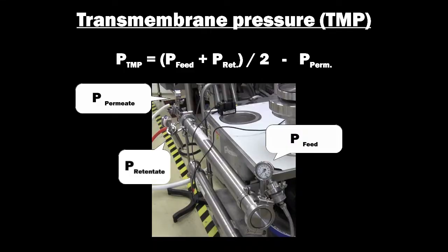The TMP can be manipulated in a couple of ways. One, adjusting the pump speed and associated feed pressure. Or two, adjusting the retentate back pressure valve to restrict retentate flow but maintain higher pressures on the feed side of the membrane.